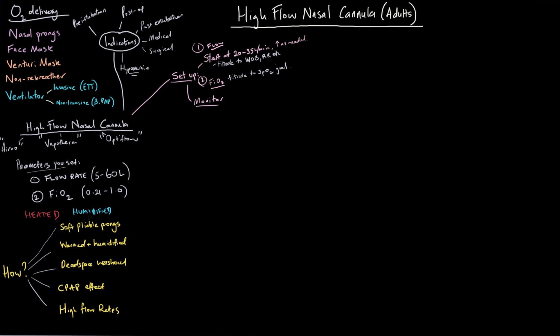Let's talk about the mechanisms by which high flow nasal oxygen helps patients. The prongs are soft and pliable, making a relatively snug fit in the patient's nose — this improves comfort compared to regular prongs and creates a small seal that reduces air entrainment and improves efficiency. The fact that the gas is warmed and humidified also reduces the patient's work of breathing and prevents nasal and upper airway dryness — without humidification, rates of epistaxis would be quite high at 60 liters per minute.